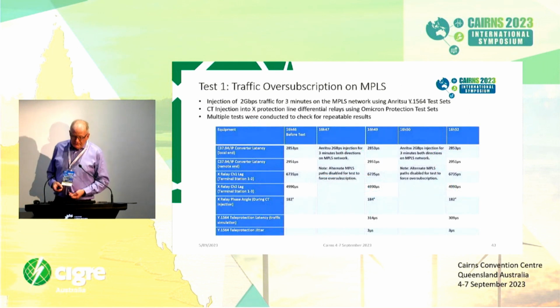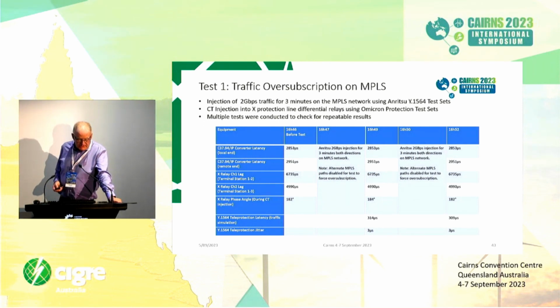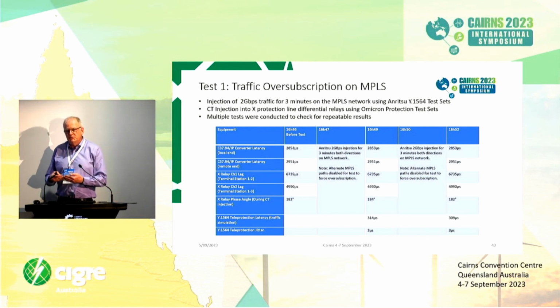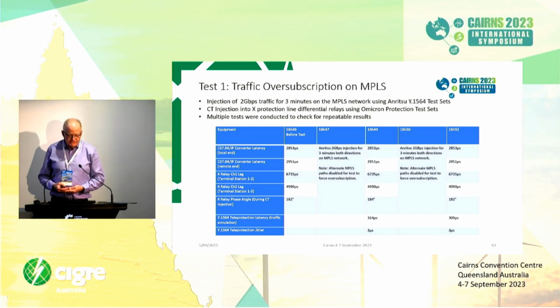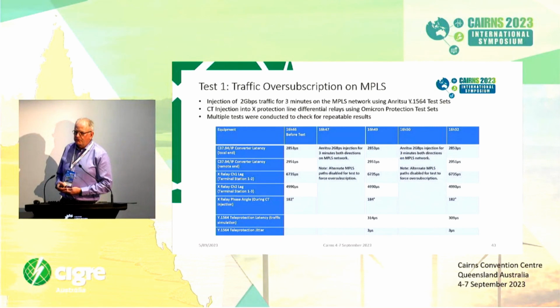So we ran through a number of tests during commissioning. Like I said, the first test we run through is an oversubscription on the MPLS network. So we inject 2 gigabit traffic on the MPLS network. For this test, by the way, we have to disable all the alternate paths on the network, just so that you're forcing the oversubscription traffic through the actual path that is also used for the teleprotection.